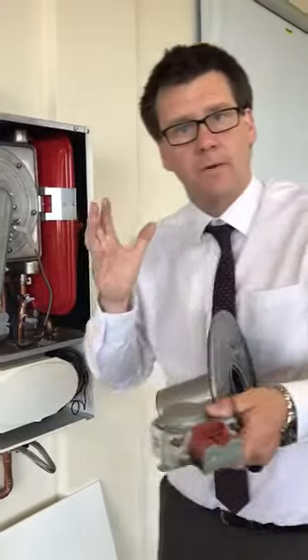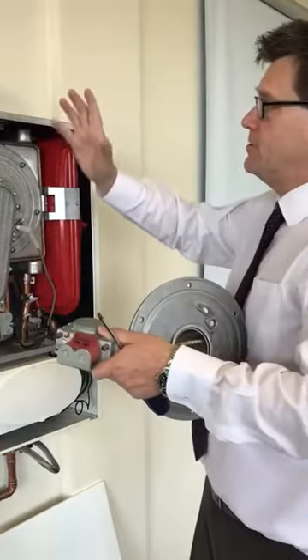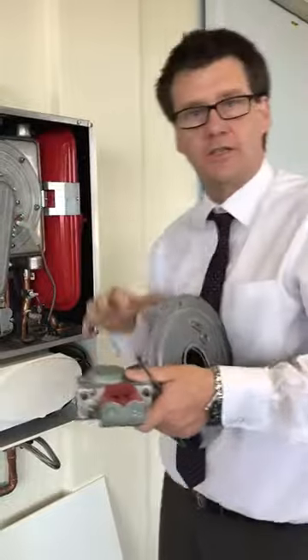So if you do get a boiler that's got some age on its back and you get a bad reading, before you start adjusting anything, make sure that you check the burner.